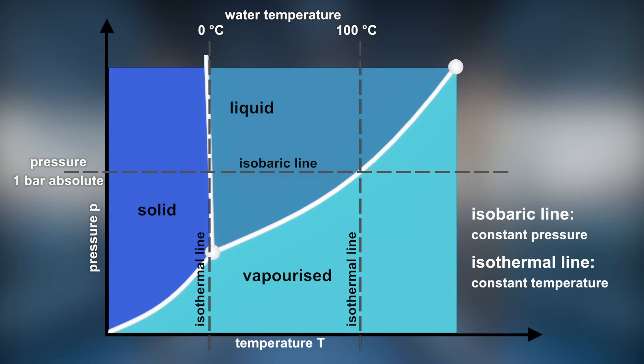Evaporation of water is not only possible when the temperature is increased at a constant pressure. The other possibility is to keep the temperature constant and reduce the pressure below the vapor pressure. Water can evaporate and condensate at temperatures below 100 degrees Celsius if a static pressure is low enough. This is exactly what happens when cavitation occurs.